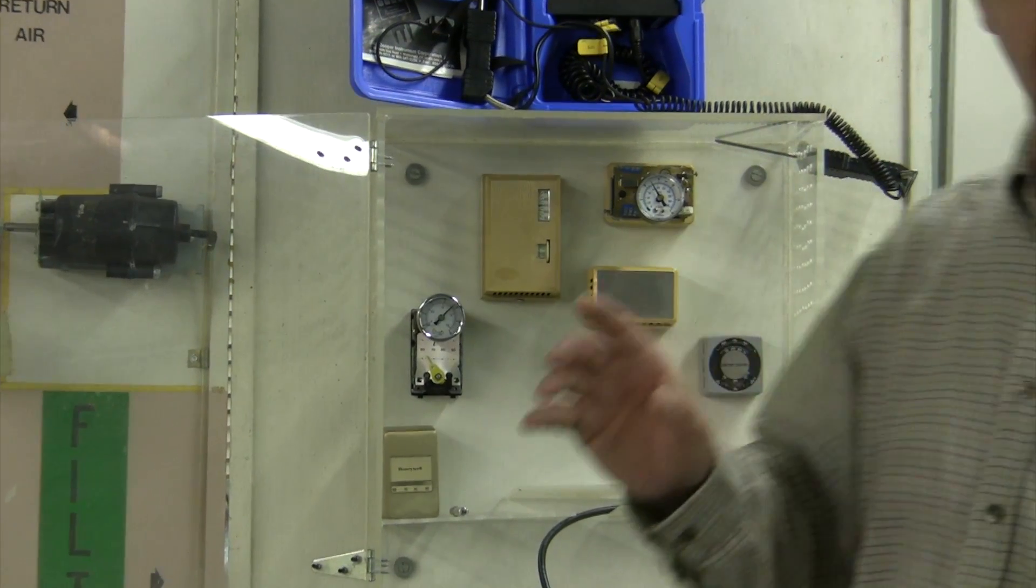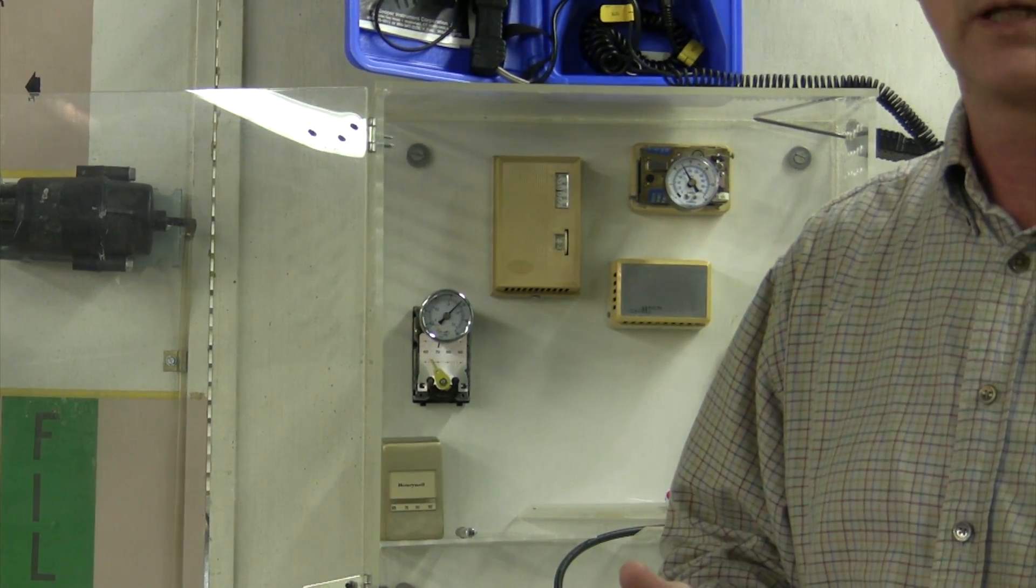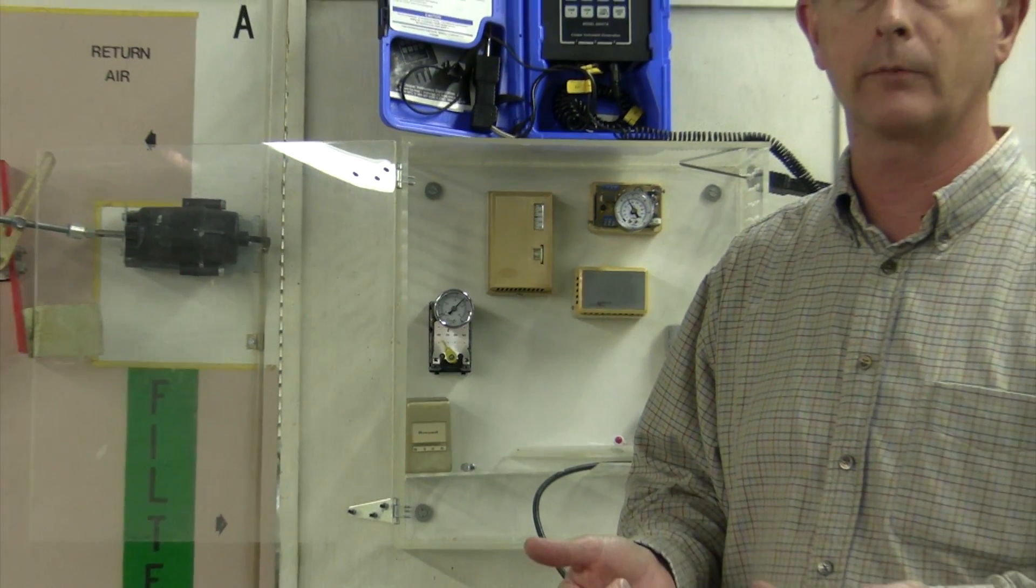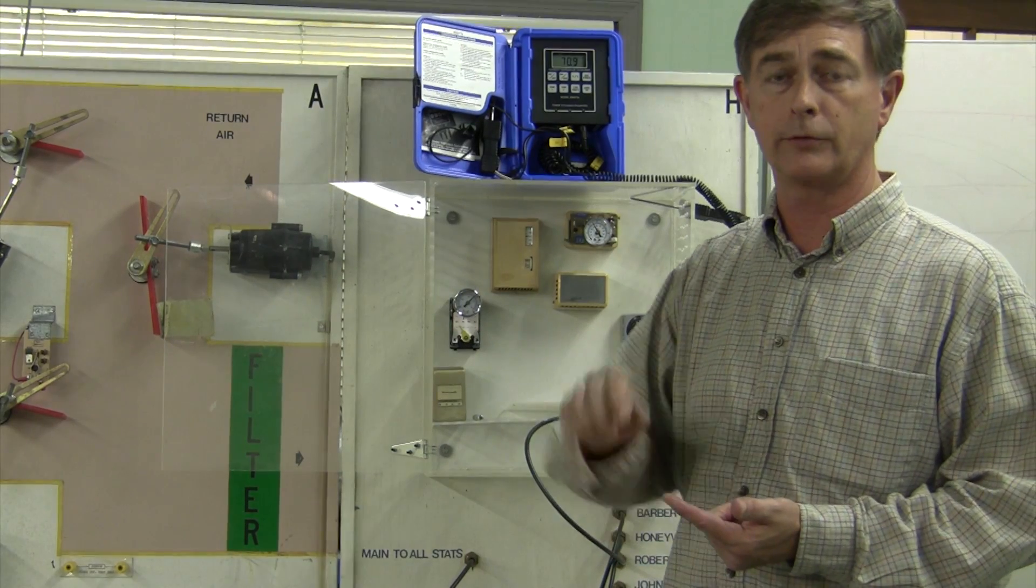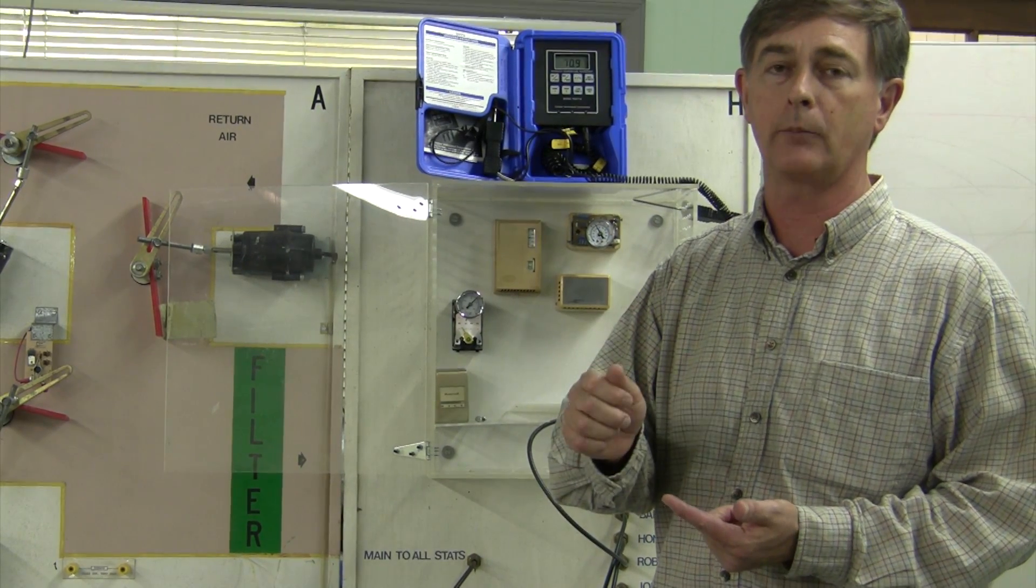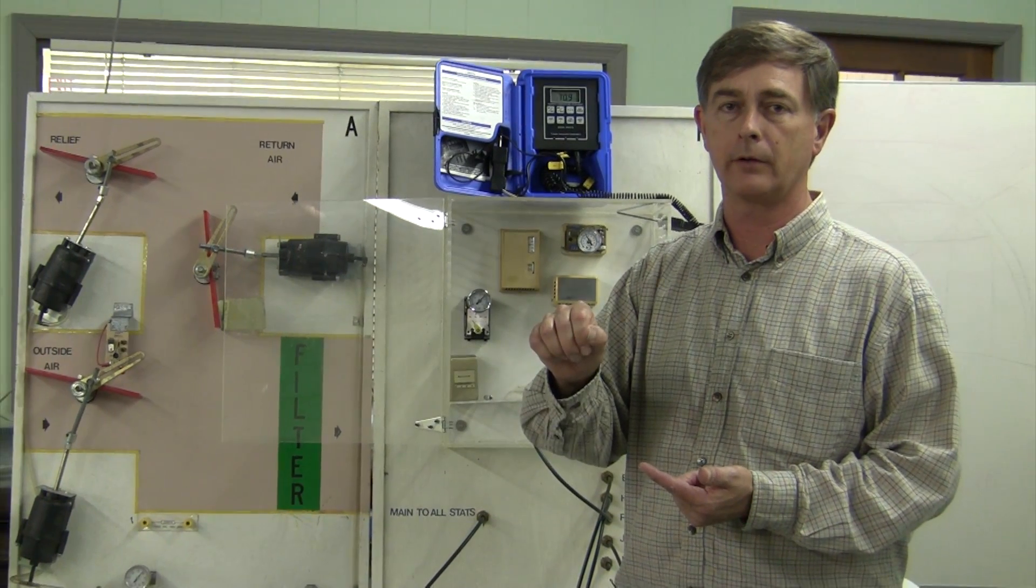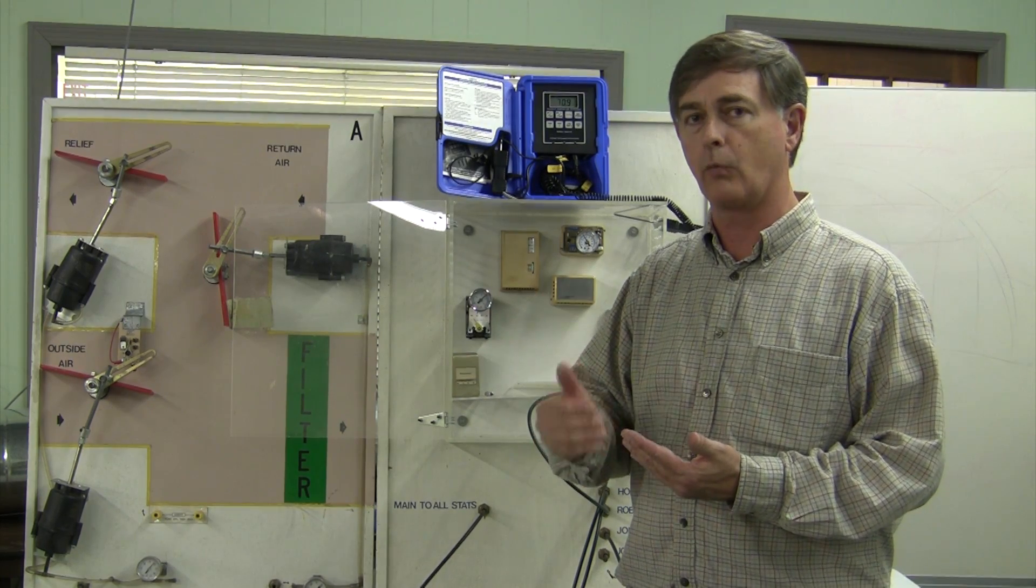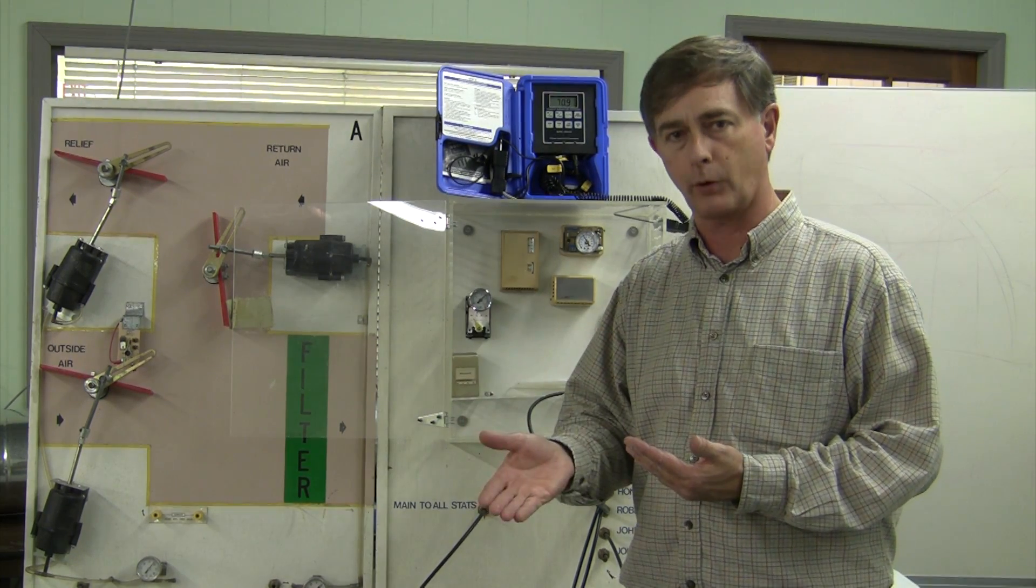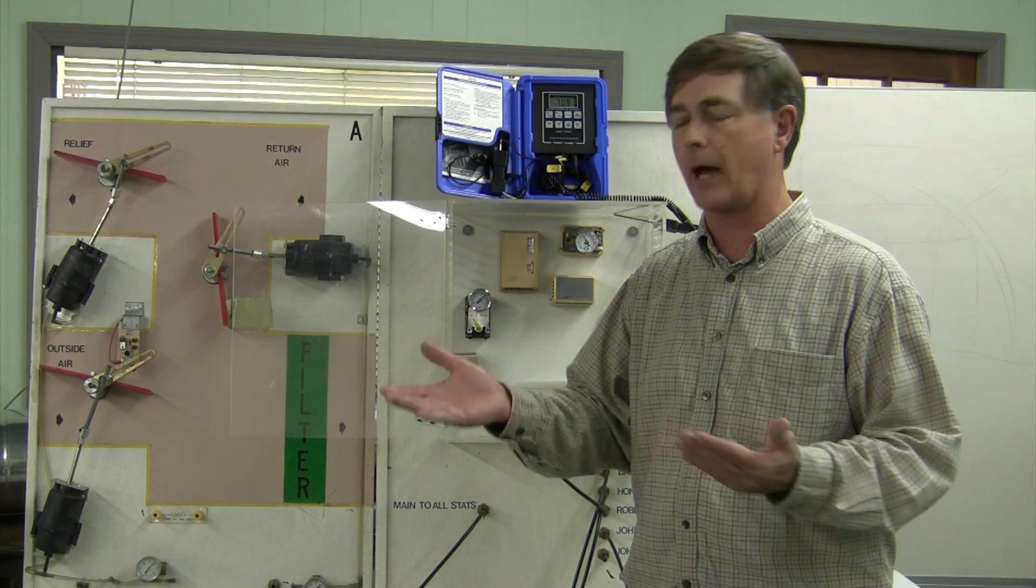First thing we're gonna do is look at the basic strategy when you want to calibrate a pneumatic thermostat. You need to check the ambient temperature of the room, set the thermostat for that ambient, and then you calibrate the thermostat to meet that ambient. When you adjust it, we need to know what output pressure, what branch pressure we expect, and that's dependent on the application.